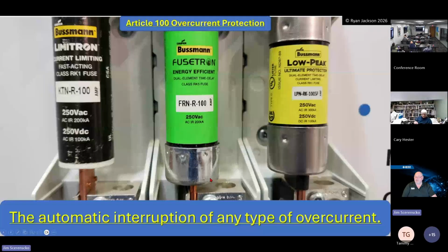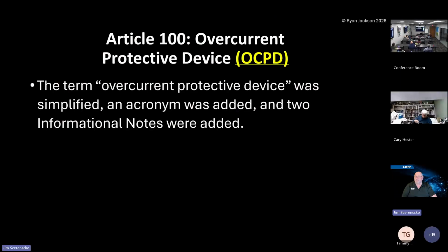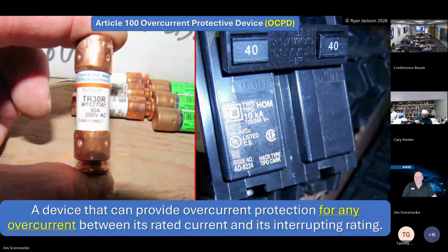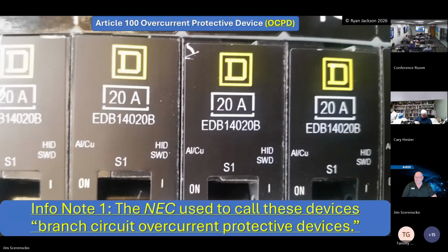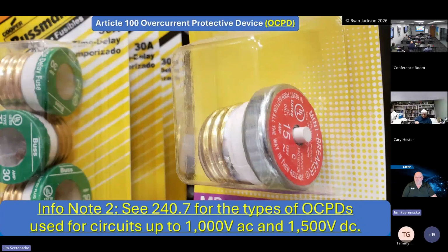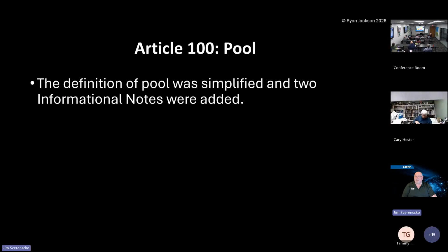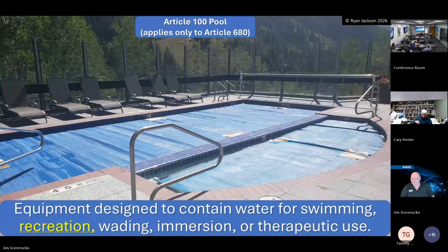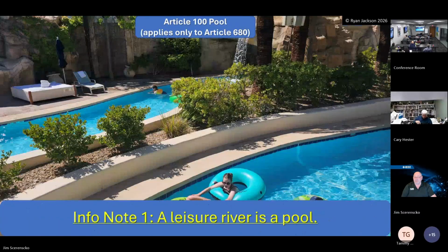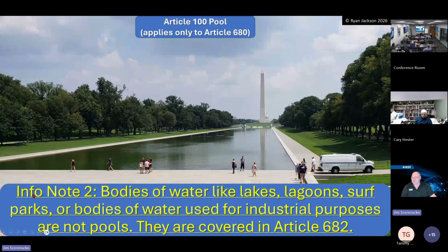Overcurrent protection was added to the definitions: the automatic interruption of any type of overcurrent. OCPD was also put in there. Branch circuit overcurrent protective devices, we have all kinds of names for them. 240.7 covers the types of OCPDs used for circuits up to 1,000 volts AC, 1,500 volts DC. For the definition of a pool, they added the word recreation: equipment designed to contain water for swimming, recreation, wading, immersion, or therapeutic use. A leisure river is a pool. It's an informational note. Pool only applies to Article 680.